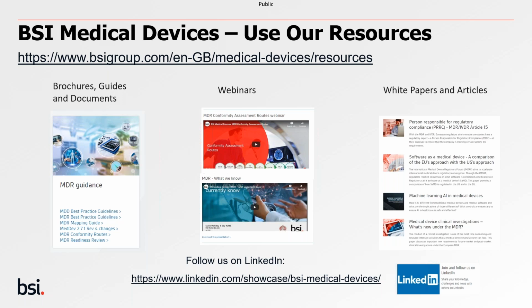And I'll just squeeze in one more question. Can you provide an example of what a justification could look like for extreme variants, and how can we evidence that with lack of data, please? Yeah, I think I went through a little bit of this on the slides. Where there's a lack of data because variants are seldom used, not because you haven't taken the appropriate actions to collect that data, then that justification could be referenced through sales volumes, through incidence of the condition, and really describing that argument as to why you have that limited data.